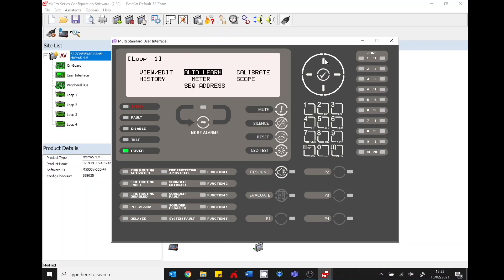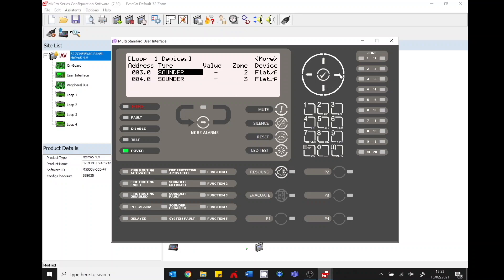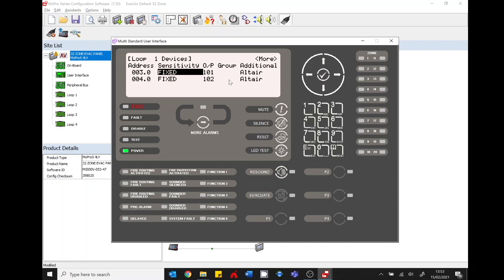If you want to add a device then you re-auto learn the system adding the device. You can view and edit devices. Same as just having an LCD display. So you've got all these different sounders devices that you can configure. Scroll to the right hand side. Assign it to a zone and put in the appropriate text. And then what you've also got is your output groups remember.